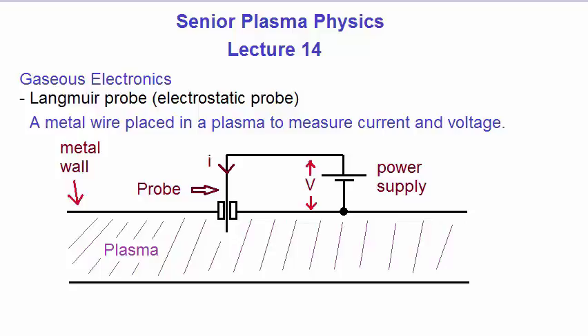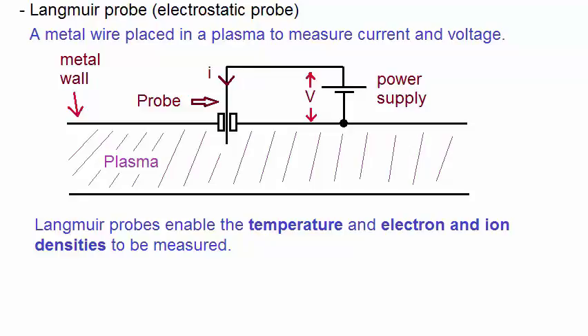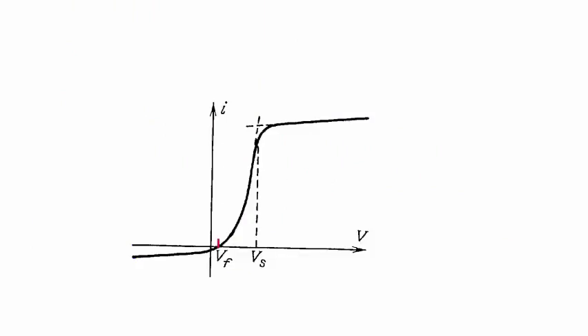Amongst other things, the Langmuir Probe enables the plasma temperature and electron and ion densities to be measured. Here is a plot of the applied voltage from the power supply and the measured current flowing through the probe.